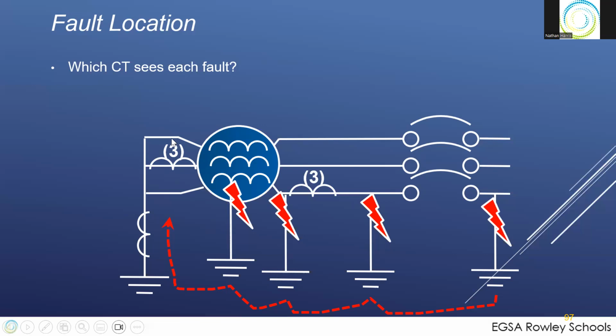So also in medium voltage machines, we'll use CTs on this side because the voltage here is 0 to ground. So we can use a low voltage CT in a medium voltage generator. First time I saw that, I about freaked out. But they do it all the time because it's so much cheaper to use a low voltage CT, and it's a lower current level.